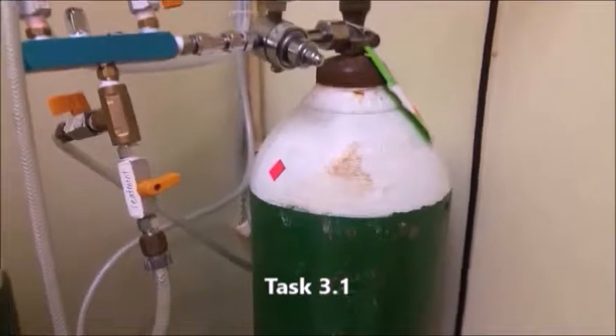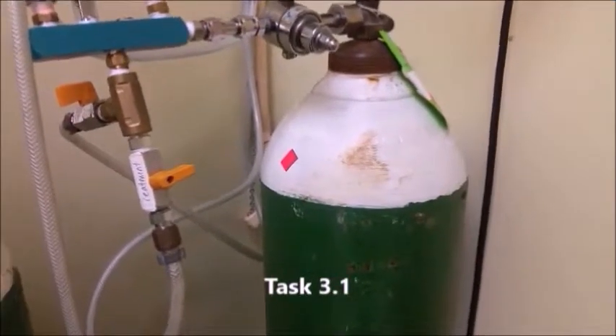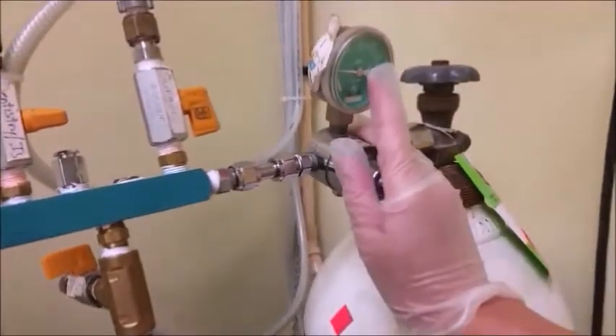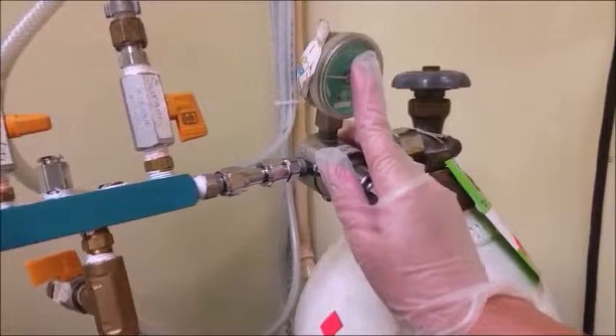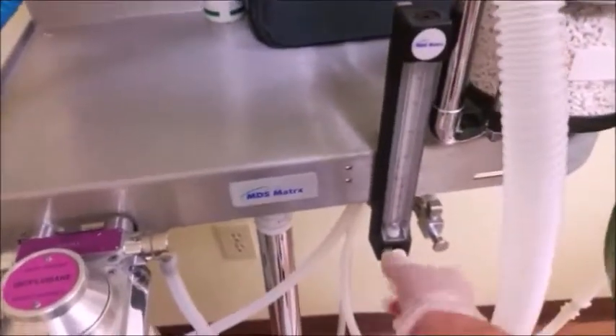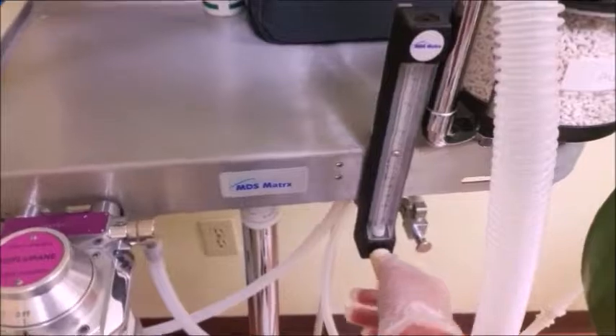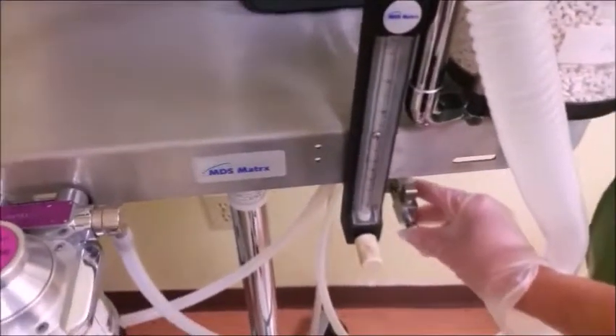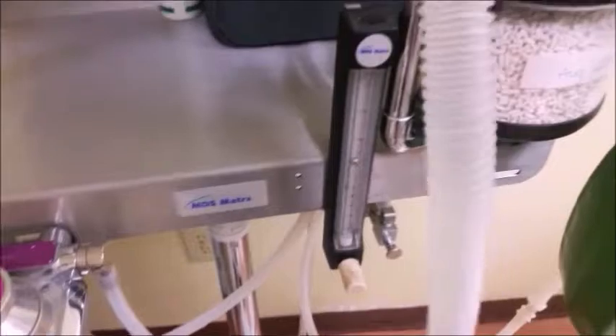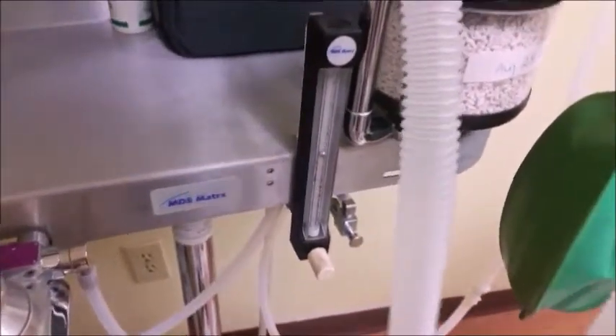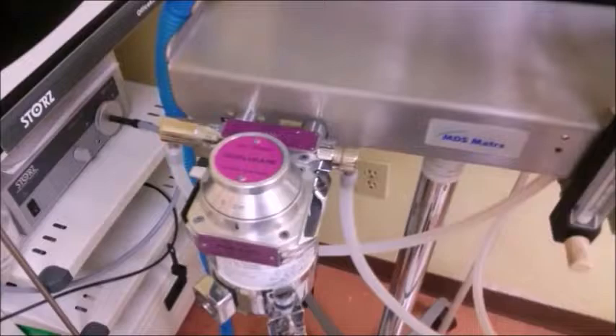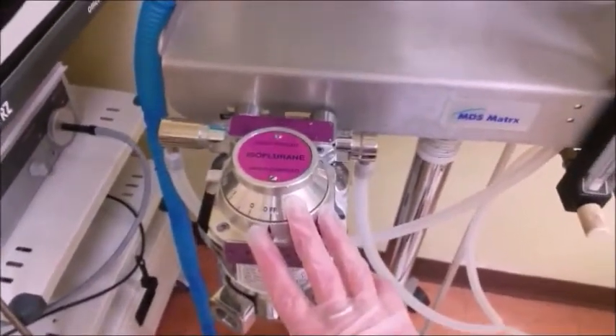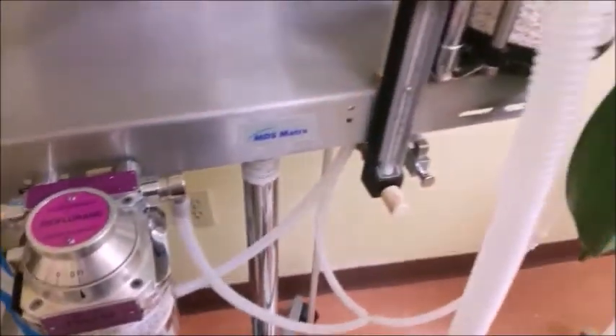Going to talk about our anesthetic machine, starting with our oxygen H canister. It is turned on at the moment. Our pressure is beginning to run a little bit low. Ideally, it should be at about 2,000 psi on our pressure meter. We then have a flow regulator. Coming over to our machine, we have our oxygen flow meter, which allows us to control the amount of oxygen being delivered through the system. We have our flush valve, which allows us to place pure oxygen into our system. We have our precision vaporizer, and we use isoflurane.